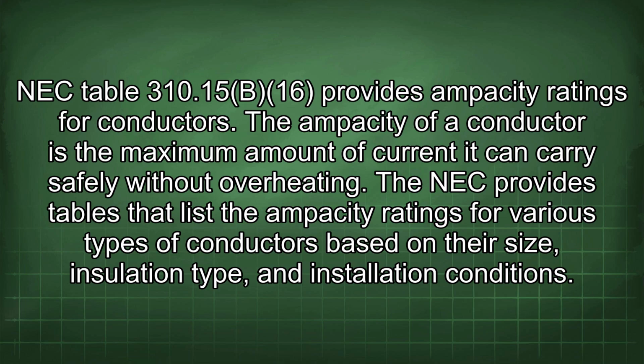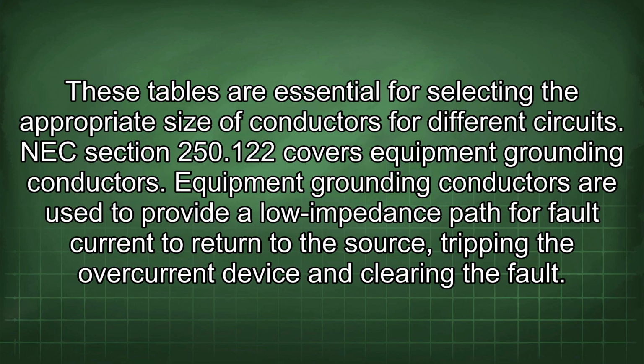NEC Table 310.15(B)(16) provides ampacity ratings for conductors. The ampacity of a conductor is the maximum amount of current it can carry safely without overheating. The NEC provides tables that list the ampacity ratings for various types of conductors based on their size, insulation type, and installation conditions. These tables are essential for selecting the appropriate size of conductors for different circuits.